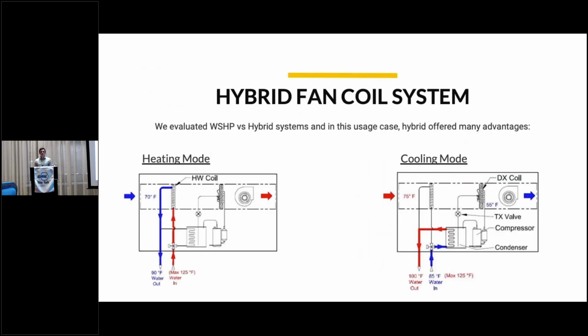These hybrid fan coils, I think, are the key to this whole project because they're able to work in 2 modes a little bit differently, but still capitalize on that 2-pipe hydronic network without too much change. In heating mode, it operates just as a normal fan coil would. It has a low temperature hot water coil that we're operating at around 105 degrees. And so hot water comes in, heats up the air, and returns back to the loop, very low temperature.